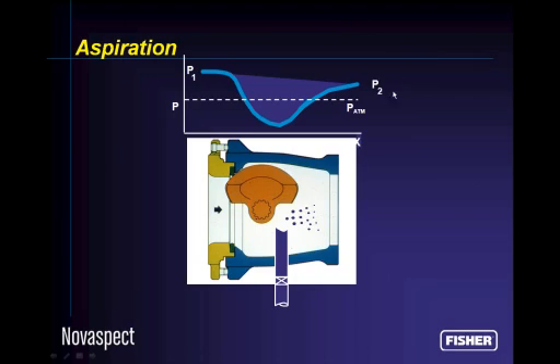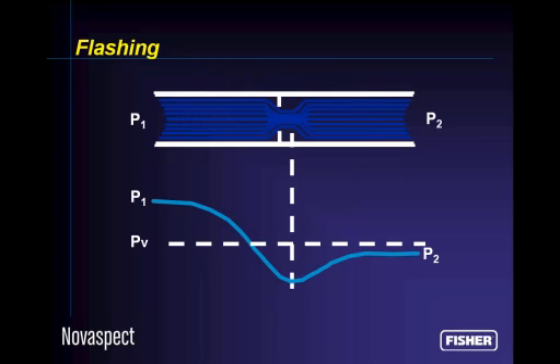So we have some positive pressure, P2, in the pipe right downstream of the valve. But inside the valve, the actual pressure at the vena contracta is less than the vapor pressure, and we would cavitate. And we have a vacuum in this particular point. We're below atmospheric pressure. So sometimes we take advantage of sticking a hole through the pipe and sucking air into the valve interior, and all these air bubbles provide sites for collapsing steam bubbles to give a shock absorber, more or less, and we reduce the effect of cavitation and flashing. That usually you would use with a very large valve, an 8, 10, 12-inch valve that's handling cooling water flow back to the river or lake. Very much less expensive than a Cav 4 that's 10-inch size.